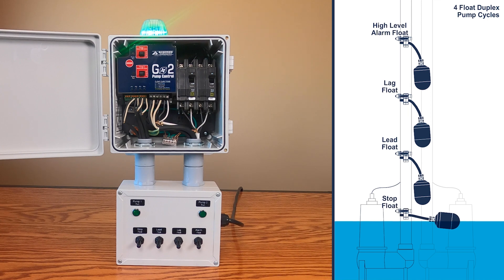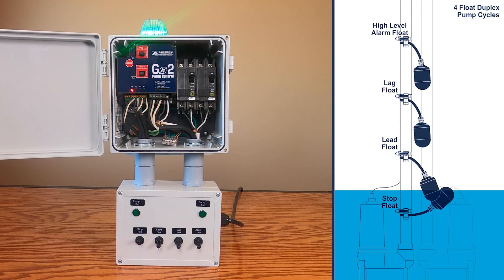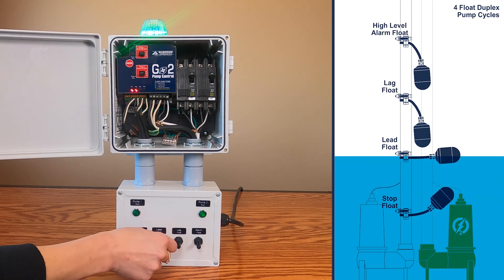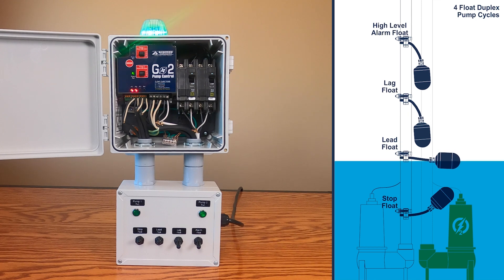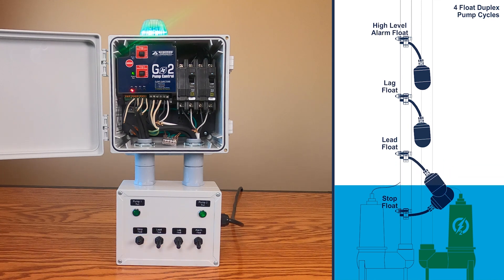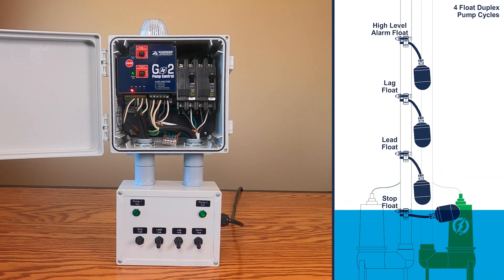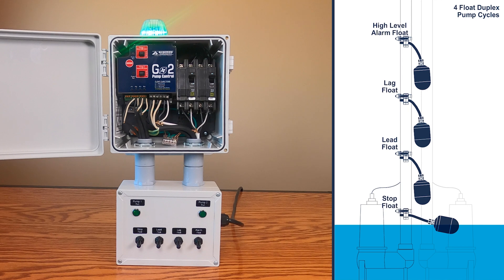As the water rises, the off float will activate. The water level continues to rise and the lead float will activate and pump 2 will turn on. Note the beacon will begin blinking indicating the pump is running. As the pump is lowering the water level, the lead float will tilt down, but the pump will remain on all the way down to the off float. This completes the pump cycle.